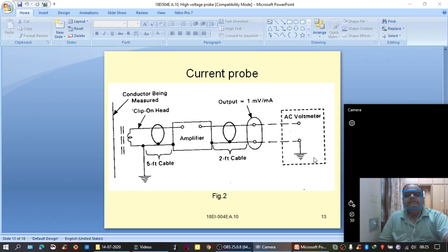Then it is connected to the AC voltmeter, and here the sensitivity is 1 millivolt per 1 milliampere. Suppose 1 milliampere is flowing here, it would be converted into 1 millivolt by using this core, and that 1 millivolt is amplified and then made available at the voltmeter. 1 millivolt as it is cannot be measured by the voltmeter, so it is amplified first, then applied. And if the meter reads 1, then dividing by 1000 gives the 1 millivolt. That is how scaling has to be fixed for the AC voltmeter.